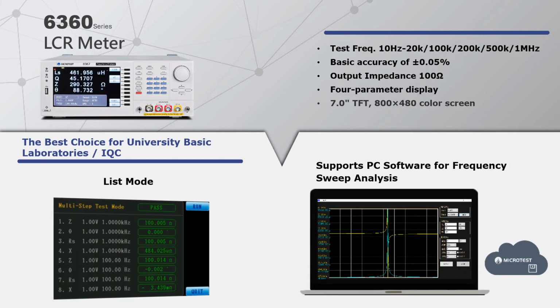The 6360 series of LCR tester is a fundamental LCR meter with test frequencies of 20,000, 100,000, 200,000, 500,000, and 1 MHz. Basic accuracy is ±0.05%, and it provides a 100 ohm output impedance. The screen displays 4 parameters set simultaneously, featuring a 7-inch color screen. Additionally, it supports PC connection software for scan and analysis, making it an efficient choice for basic laboratory experiments and quality inspections.